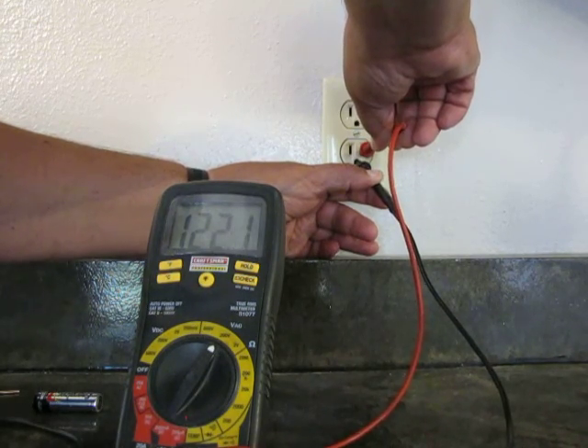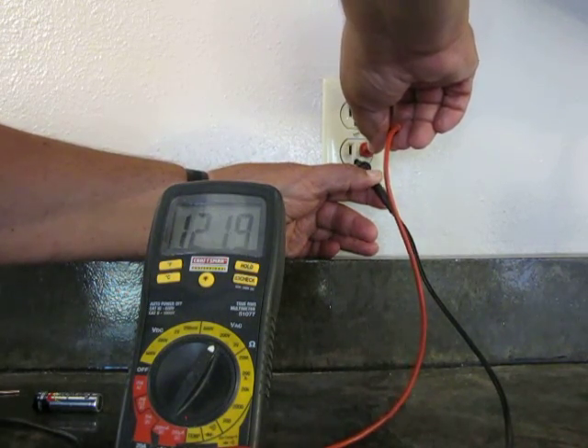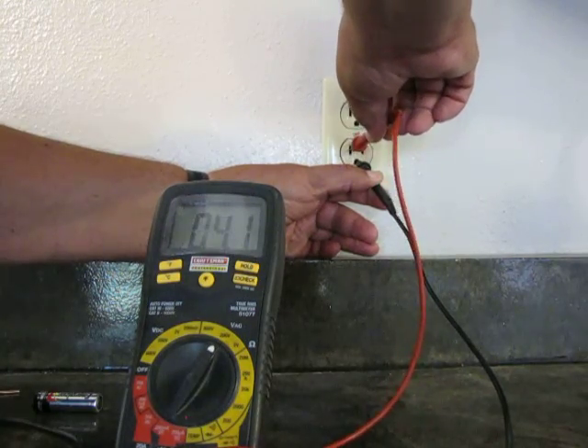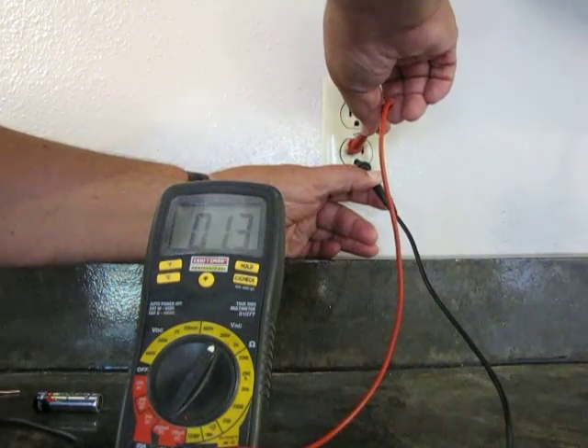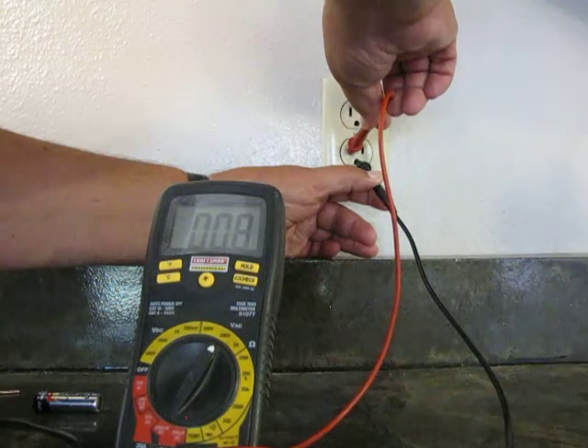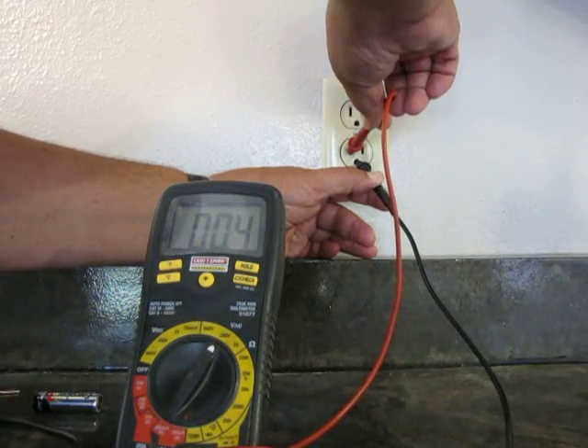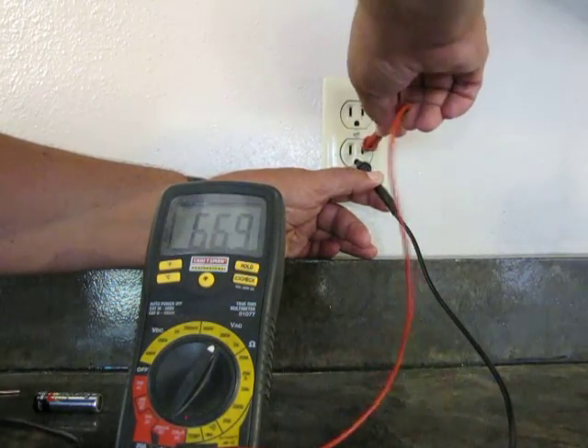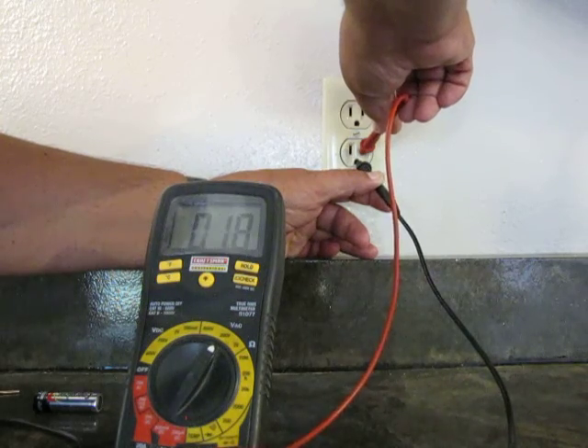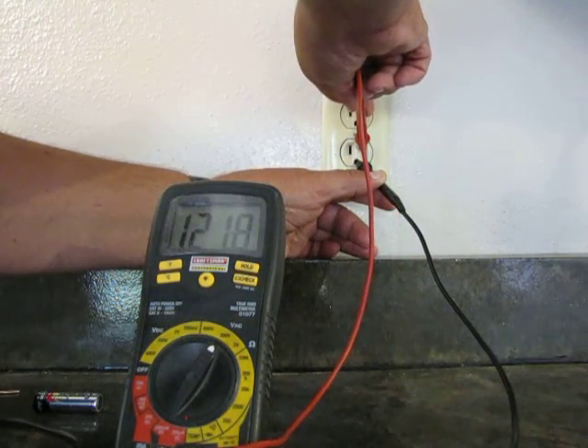Typically most of your providers will overrange about 10%, that's fine. We go to the neutral side, this would be the white wire on the back of the outlet. I have no voltage. This would be the black wire on the back of your outlet, and once again I have my 122 volts.